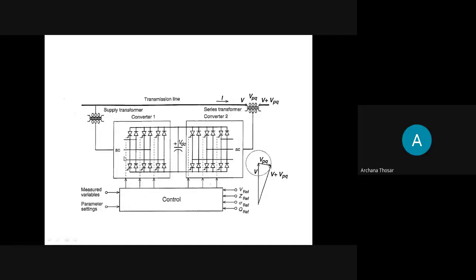As they are connected together by this DC link, and have a common connection at the AC side, the real power can be exchanged through this AC line. By the gating pattern of converter 1 and 2 from the control system - generated by comparing reactive power and the reactive components of voltage and current - converter 1 and 2 can independently generate the reactive power as desired. So there is both real power exchange and reactive power exchange.